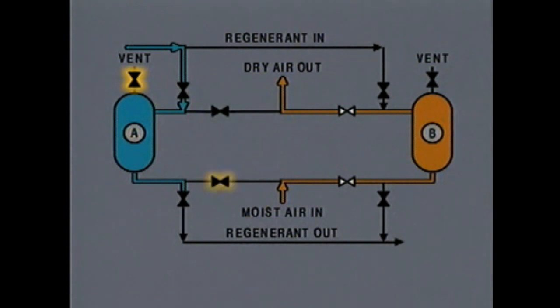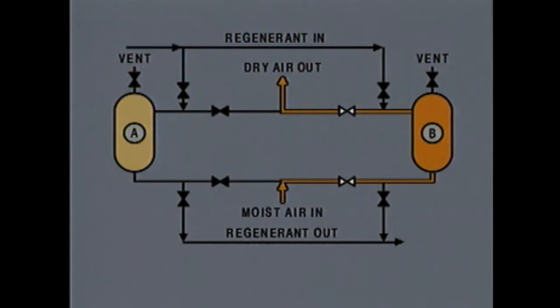This vent valve and this moist air inlet valve are opened to allow moist air to purge the regenerant from dryer A. Then the valves are closed. Dryer A is now ready to be returned to service. Successfully rerouting flows while a system is operating depends on knowing exactly which valves have to be repositioned and in what order. Using a flow diagram can make the job easier.